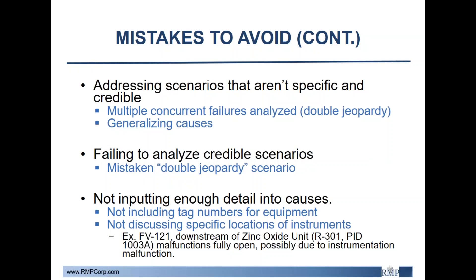Another mistake to avoid is addressing scenarios that aren't specific and credible. One example would be analyzing a double jeopardy scenario where multiple independent failures are occurring simultaneously — this is not considered credible and shouldn't be addressed. In contrast, avoid generalizing causes so much that you don't know what is being discussed. You always need to say more than just 'valve upstream of reactor,' as this could refer to a number of things.